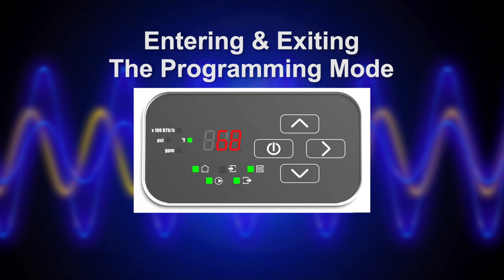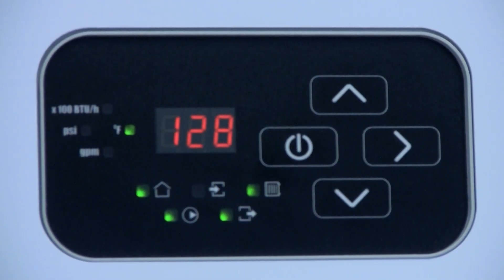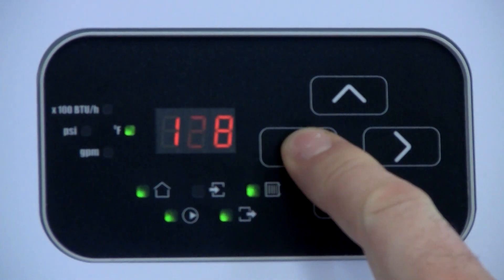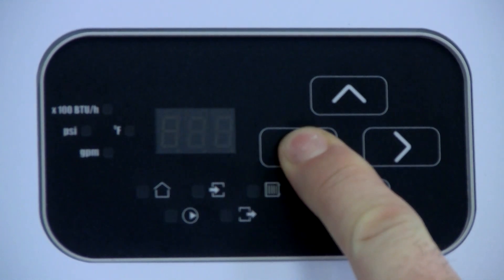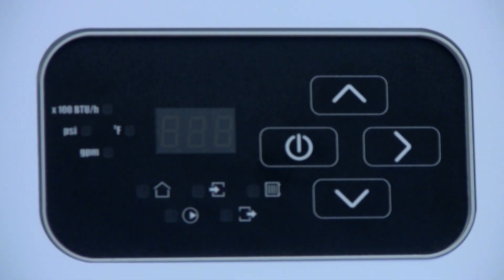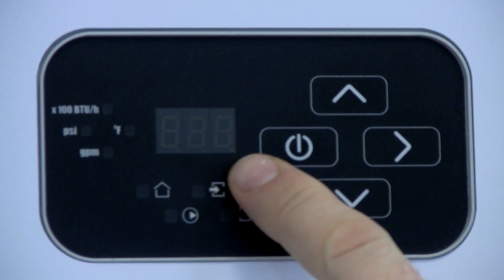Entering and Exiting the Program Mode. To enter the programming level, you must first put the boiler into standby. This is done by pushing and holding the standby button until the display goes blank. You will know that you have correctly entered the standby mode because the display will be blank with the exception of a flashing red dot on the bottom right-hand corner.